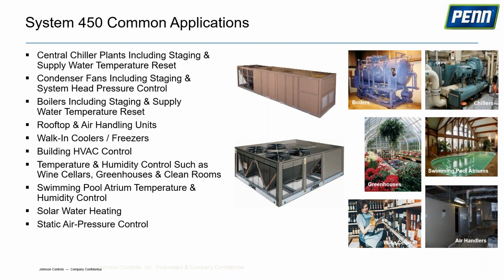The two here, they don't necessarily have to be this large of a boiler or chiller, but they can be used for staging chillers and also with outdoor reset. So you can reset the water loop temperature based on the outdoor temperature, saving energy. The same thing for boilers. This is a large boiler here, but they're used on quite a few modular boilers that are used in apartment buildings or other types of central boiler plants, where you can stage boilers based on demand and again have an outdoor reset capability, whereas the temperature gets milder outside, you reset that return water or loop temperature, again, to save energy. Condenser fans in refrigeration, both staging and system head pressure controls, is another common application.